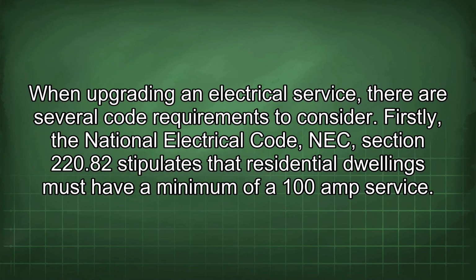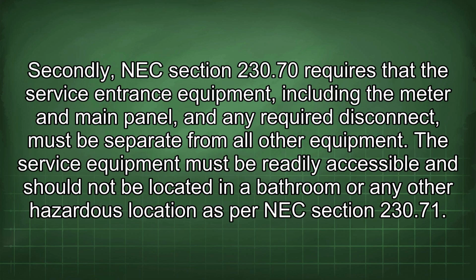When upgrading an electrical service, there are several code requirements to consider. Firstly, the National Electrical Code, NEC, Section 220.82 stipulates that residential dwellings must have a minimum of a 100 amp service. Secondly, NEC Section 230.70 requires that the service entrance equipment, including the meter and main panel and any required disconnect, must be separate from all other equipment.